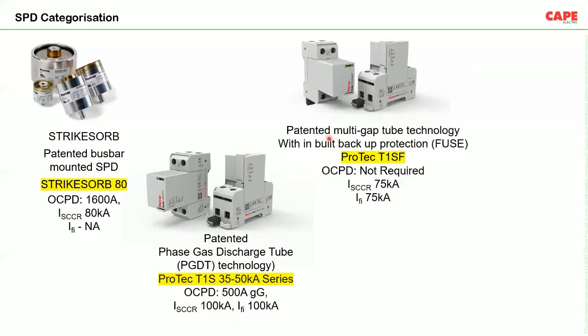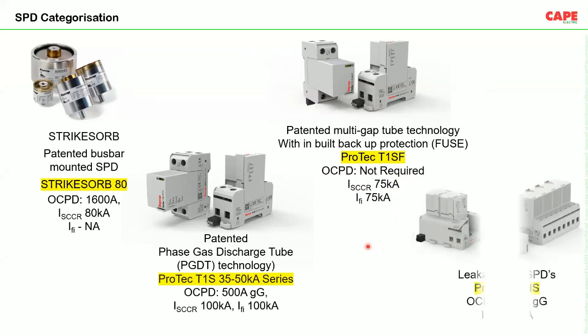The third device is called multi-gap tube technology. In this case, there is inbuilt backup protection. There is an additional fuse integrated inside the device. Model number is ProTec T1SF, for example. Here, the OCPD is not required. The backup protection is not required. Short circuit current rating is 75 kiloampere. Follow current rating is 75 kiloampere.